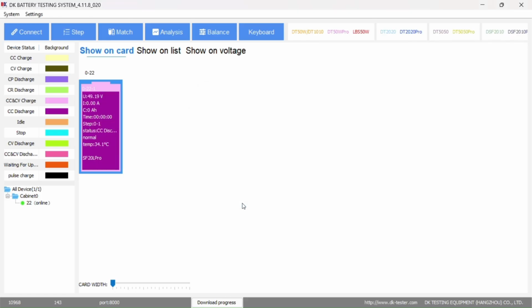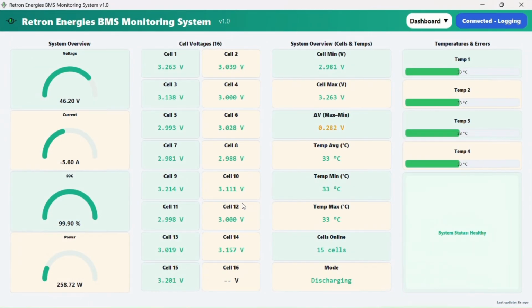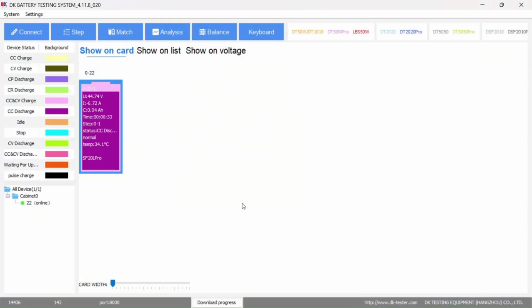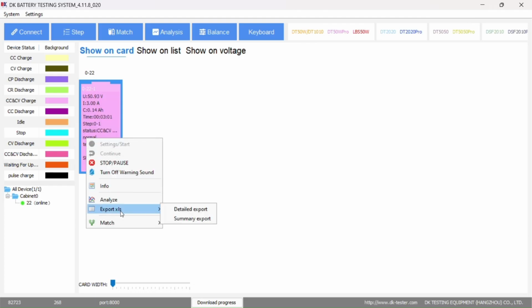Once the test begins, the system automatically executes each step according to the program sequence. The software provides different color indications for each step, allowing us to easily identify whether the battery pack is currently discharging, resting, charging, or has completed the test. During the testing process, we can also evaluate the temperature monitoring capability of the BMS by observing the temperature data and the BMS response under varying conditions. Throughout the entire test cycle, all battery parameters are continuously recorded.